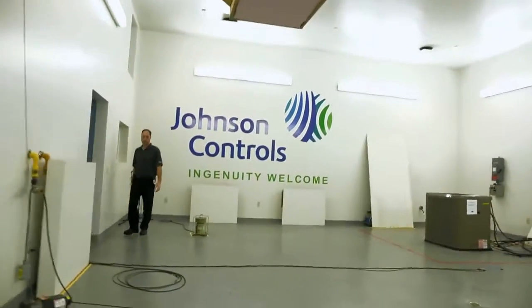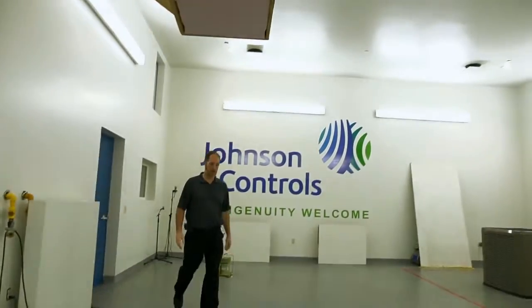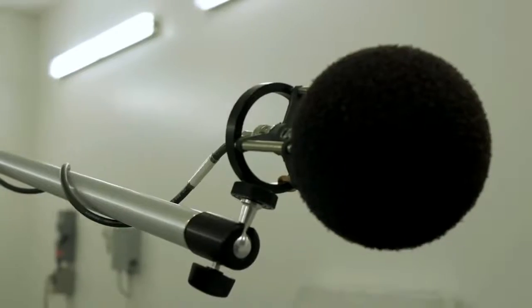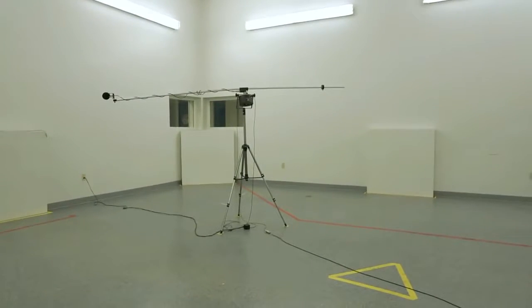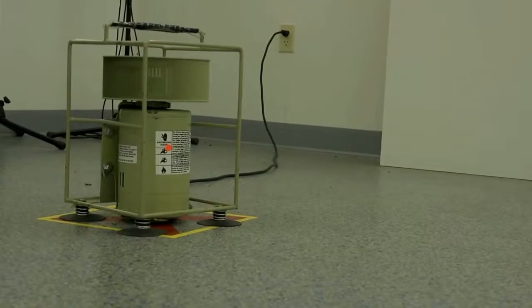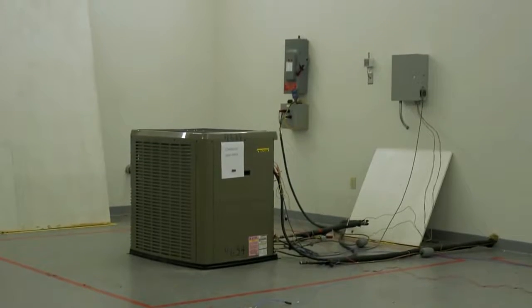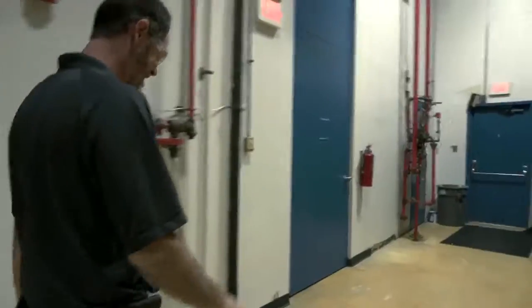So this is the sound room. It's a reverberant sound room. No matter where you go inside this room, you'll get almost identical sound volumes. The sound travels in 360 degrees around. When we test on the outdoor products, we're testing for the radiated sound, vibration that would eventually make its way into causing loose screws or broken tubing or any of those other adverse effects of vibration.